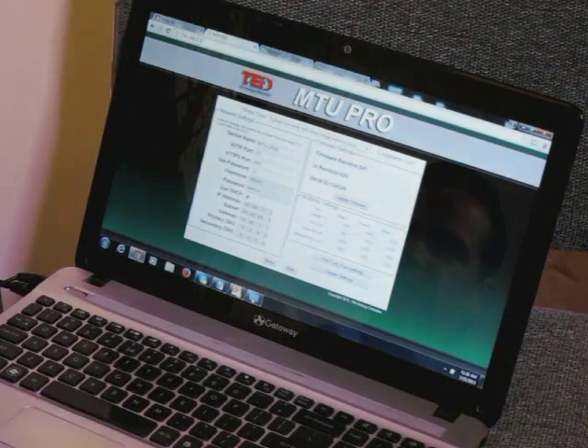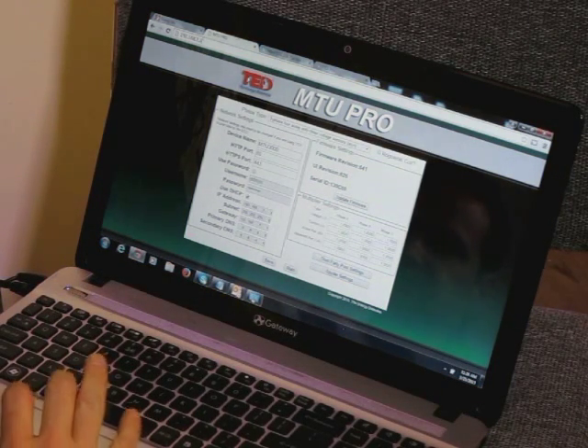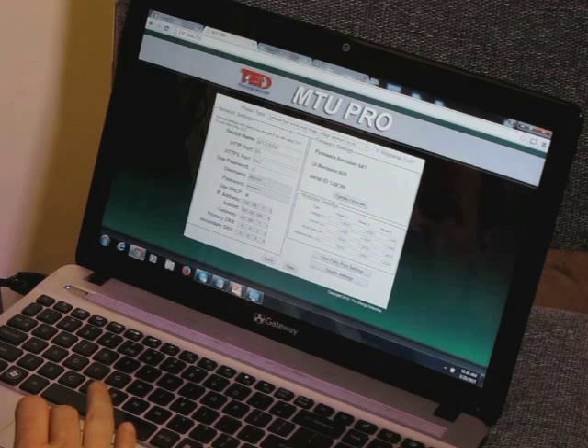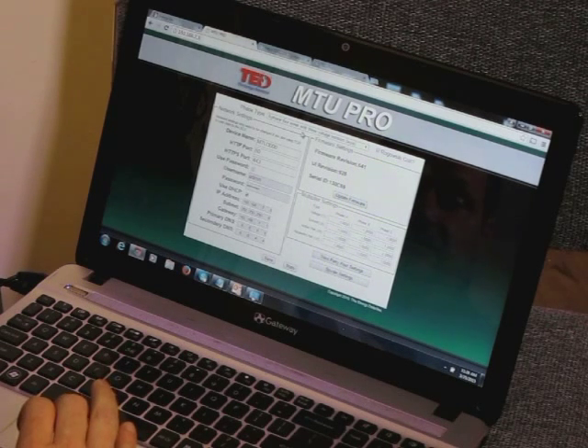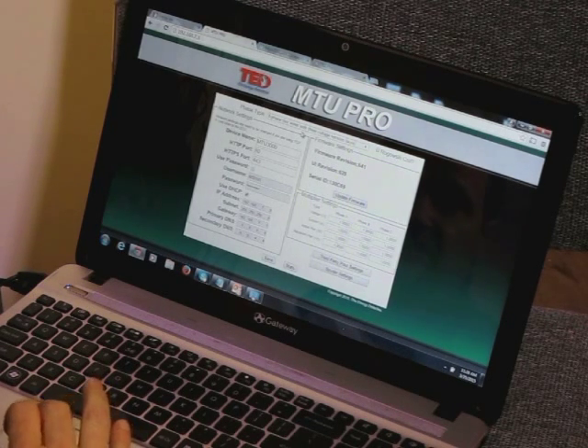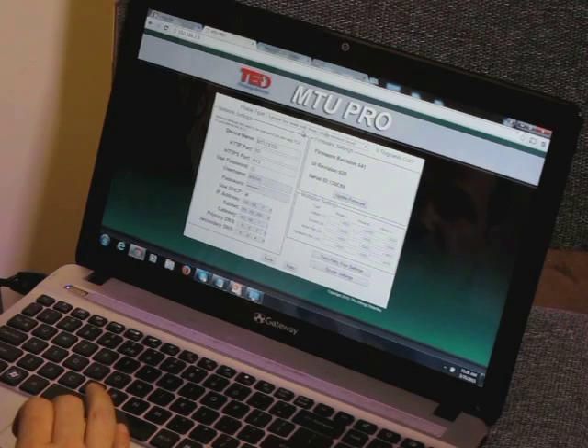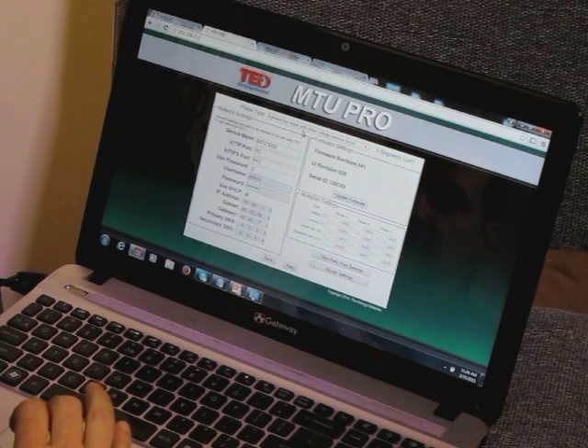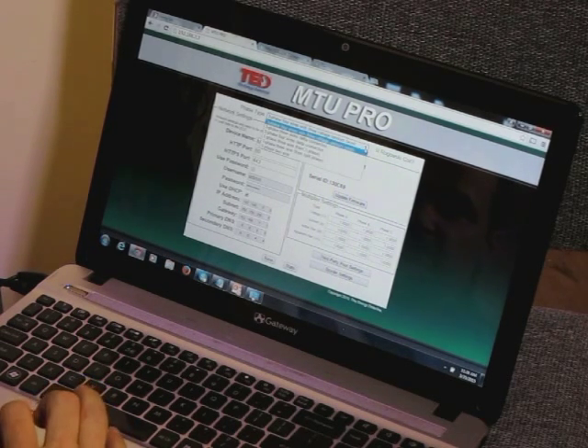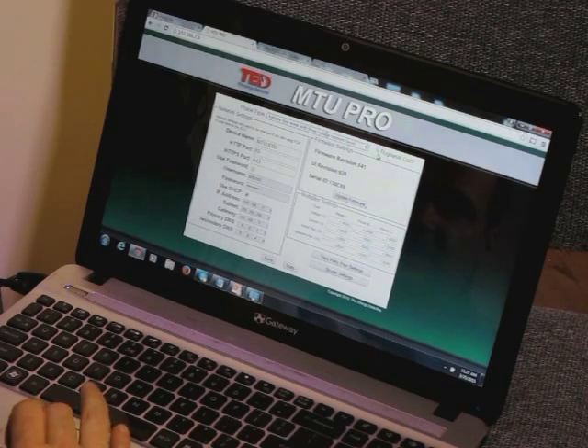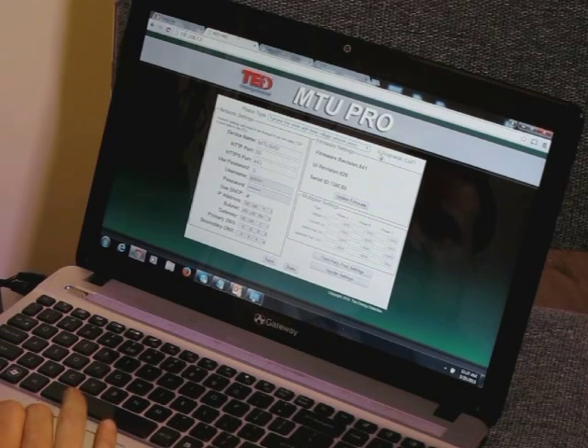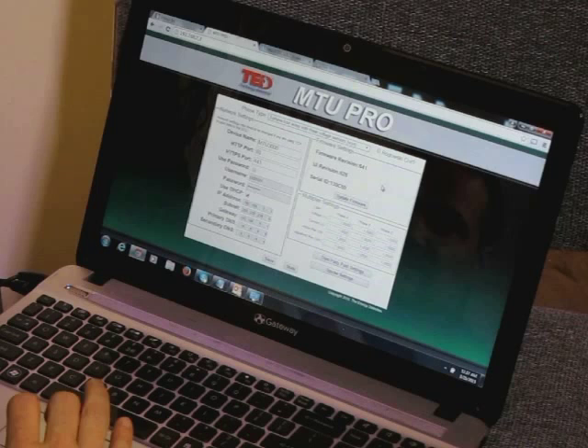And that brings up what we call the MTU's user interface page or UI page. This page is also important if you're using another configuration other than the default which is three phase four wire Y. If you were using another configuration you would select it there. If you were using Rogowski coils you would select that check box.